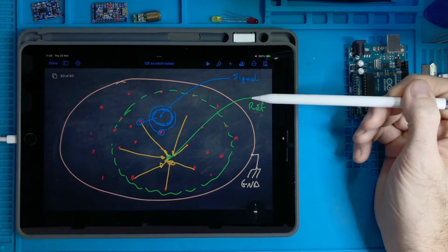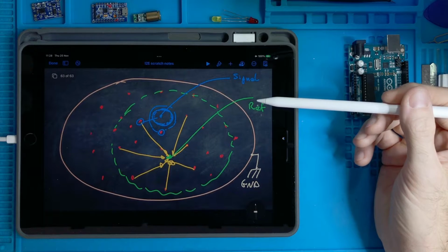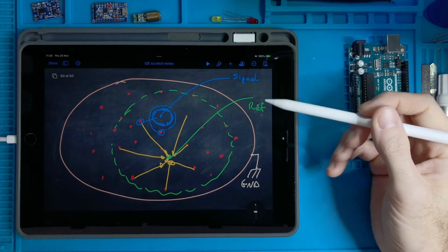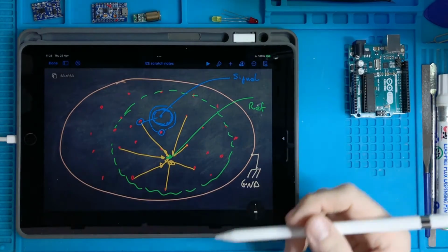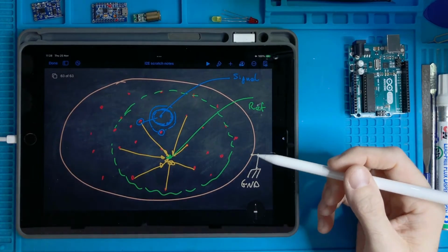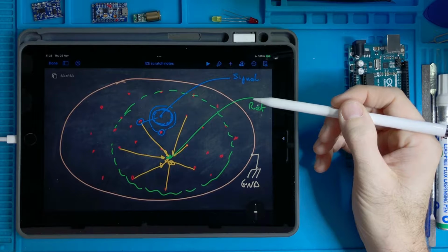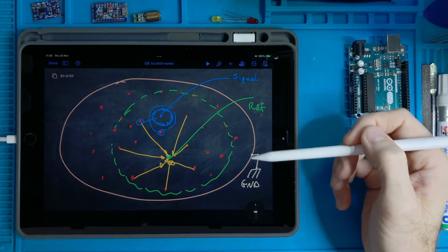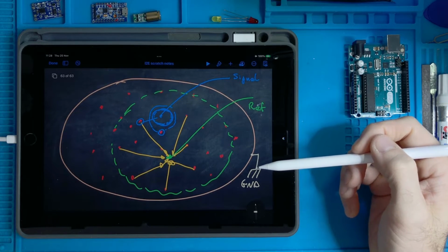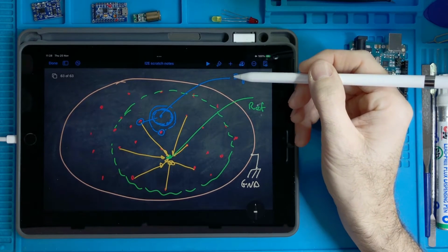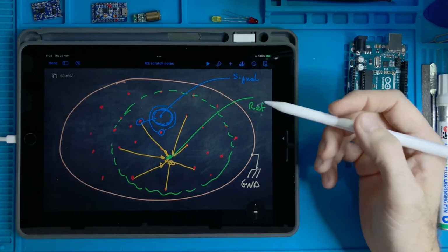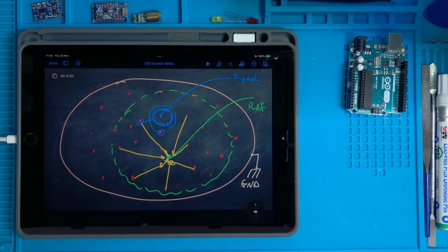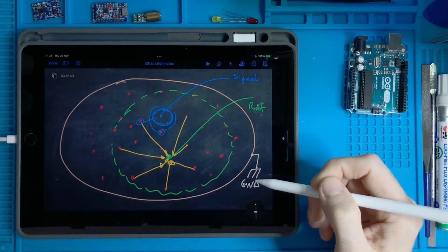but they are both voltages, so they have to be referred to a common 0 point that we call ground. So in fact, one voltage is the voltage difference between the reference and ground. The other voltage is the one between signal and ground, and the differential amplifier takes the difference of those two differences. So this ground electrode is important. We cannot disconnect it.